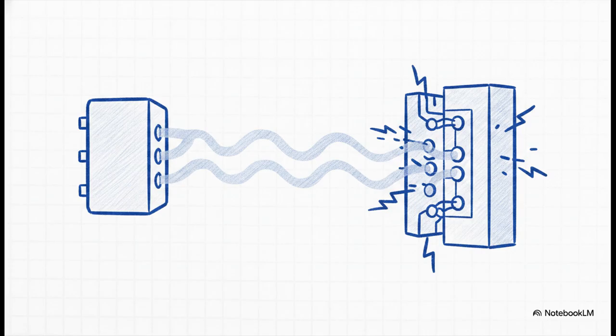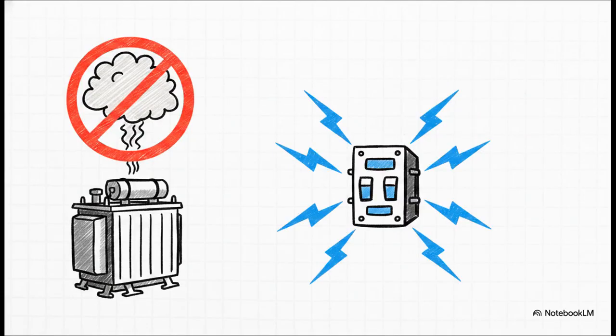In those tightly packed electrical rooms, the atmosphere gets hot, right? Over time, silicone-based materials can actually off-gas, migrate right through the air, and settle on sensitive electrical contacts and really expensive switchgear nearby. It literally insulates those contacts and ruins them. It's basically a silent, invisible killer of electrical reliability. But by using absolute zero silicone in its construction, the RESIBLOC prevents that compound migration entirely. For a commissioning engineer, specifying this zero silicone design completely eliminates a known offshore reliability problem right at the source. You don't have to plan tricky maintenance around it, and you don't need expensive mitigations down the line. Why? Because you've engineered the risk entirely out of the room from day one.